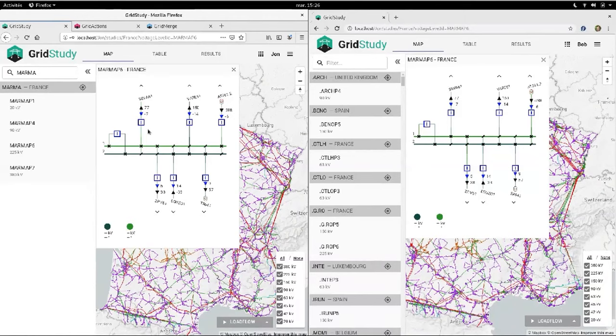Let me also open this breaker here, which should, after we recomputed the values, show that the power is no longer 77 megawatts flowing through this line, but instead it should be zero because the line has become disconnected. Let's run the load flow.